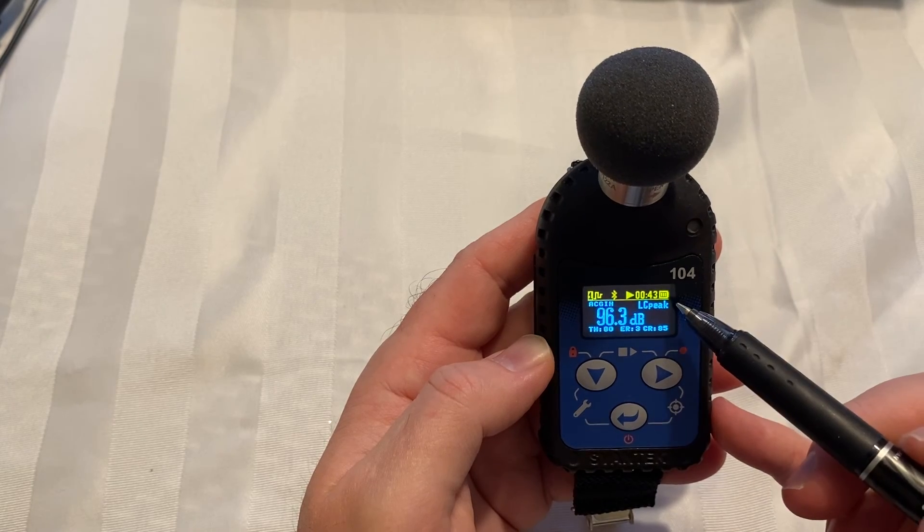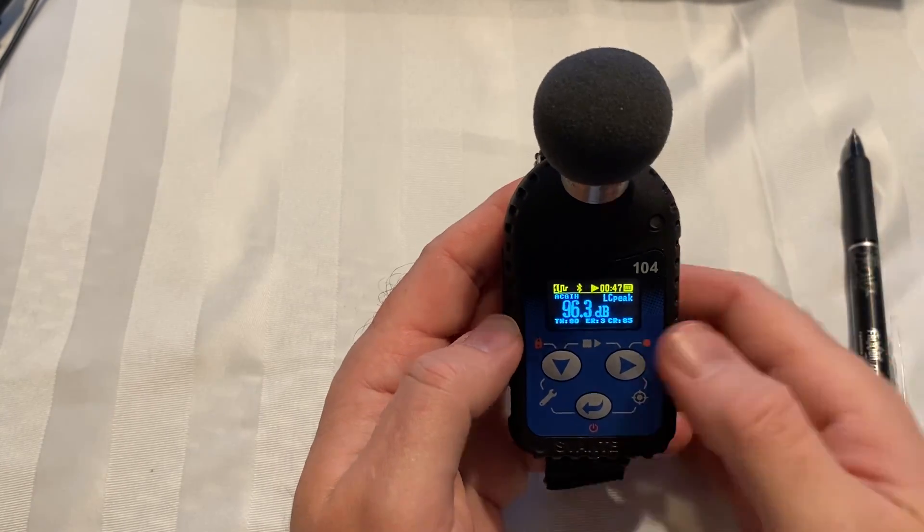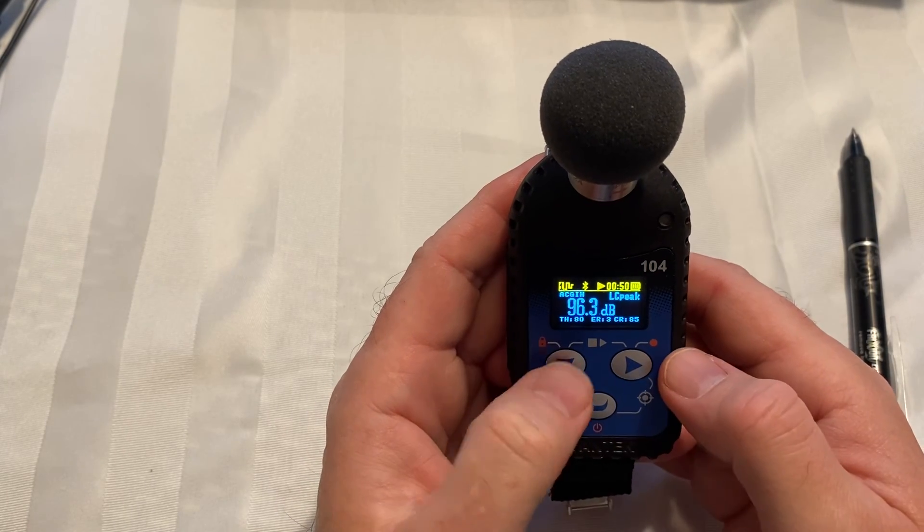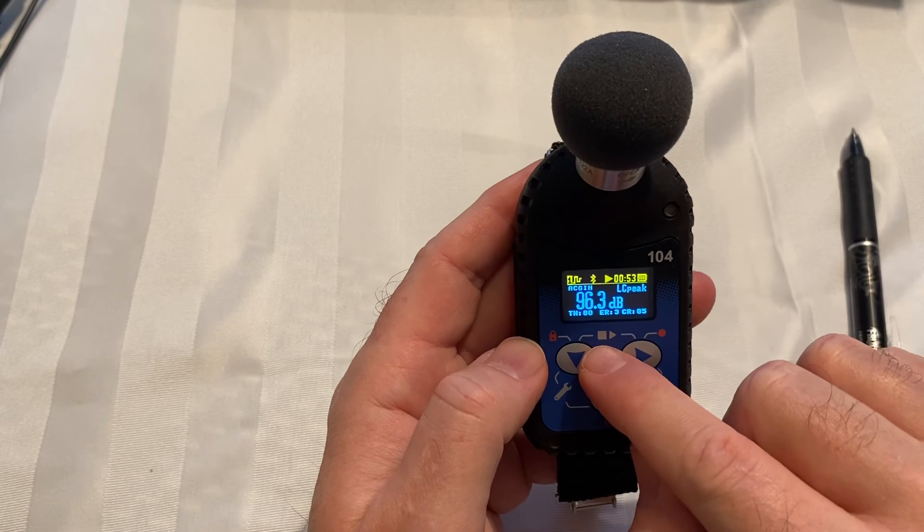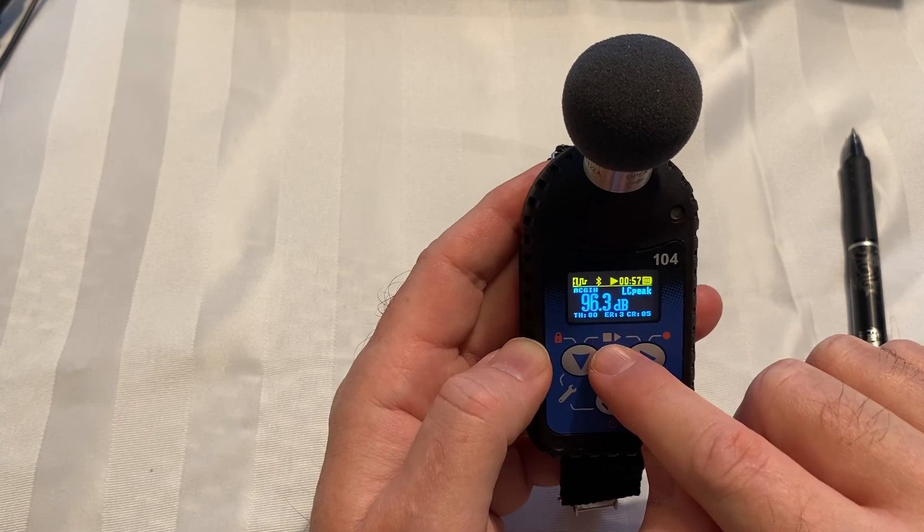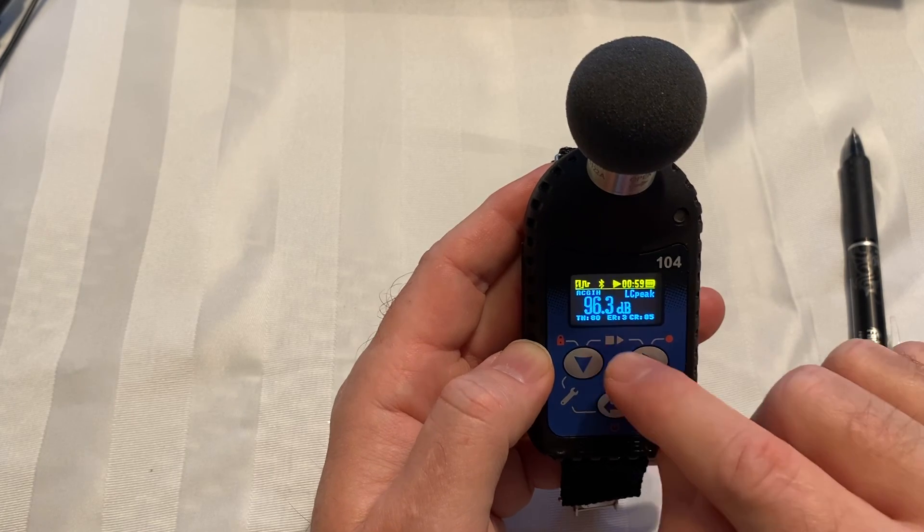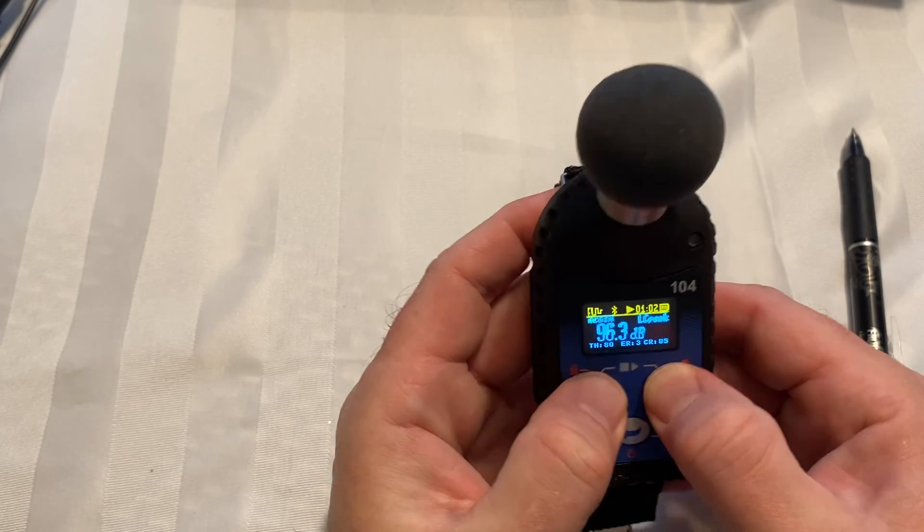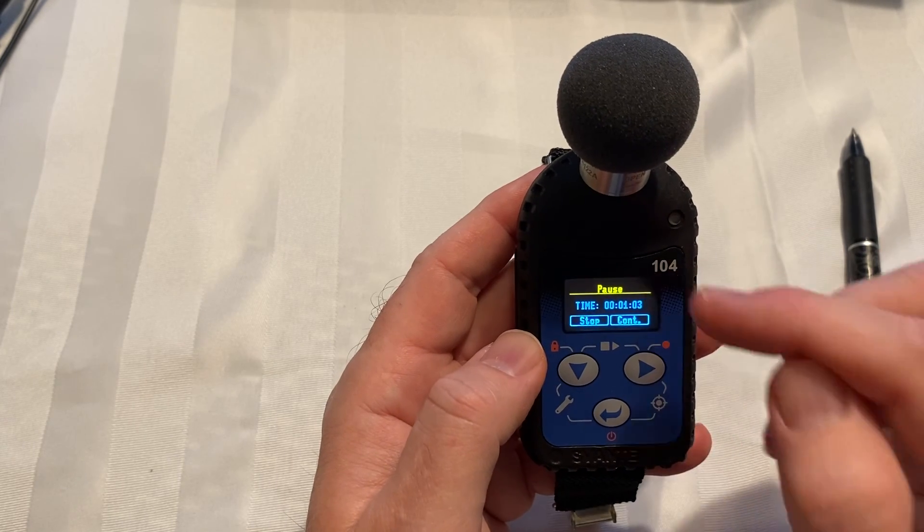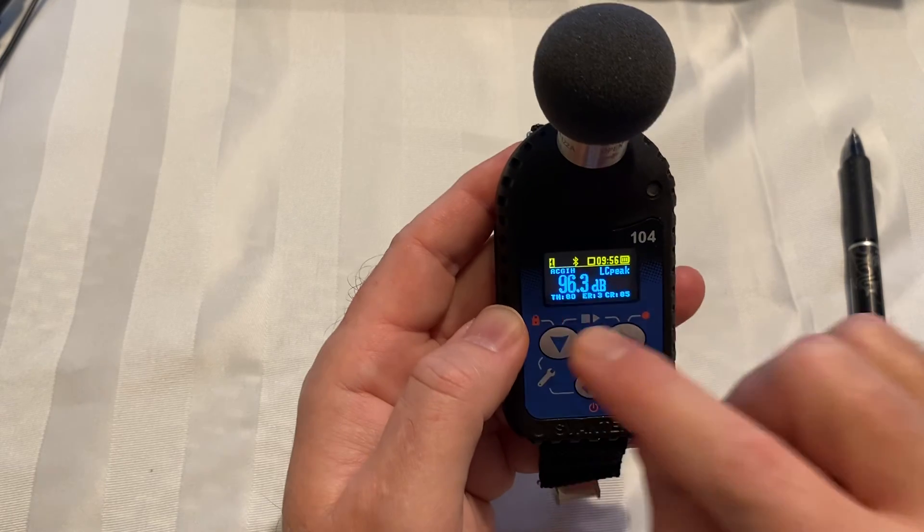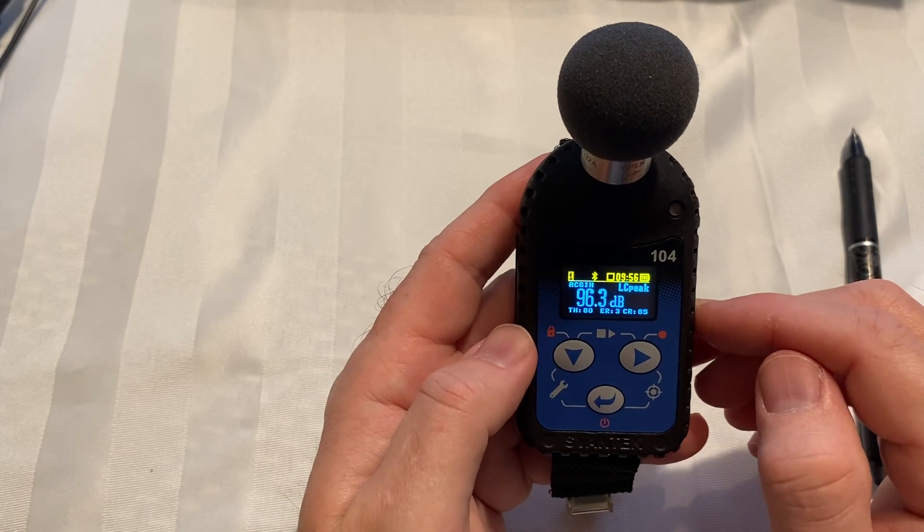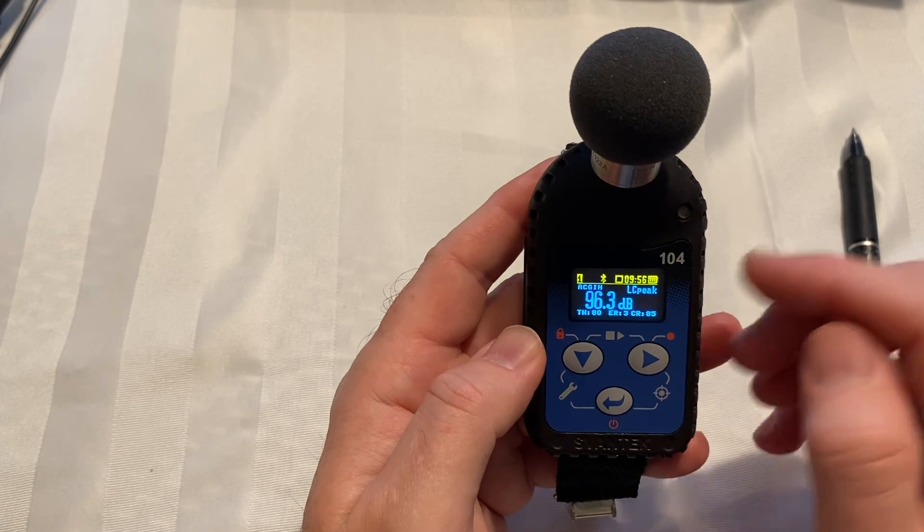So if I want to stop this run right now, I could hit the down and right key. Again, these two keys together can start the run or start the recording and stop it. The square is to stop, the triangle means it's running. So if I hit these two together, it'll pause it right now, but I could either continue or I can stop. I want to stop. And so that's the basic overview of the buttons and some of the features of the dosimeter.